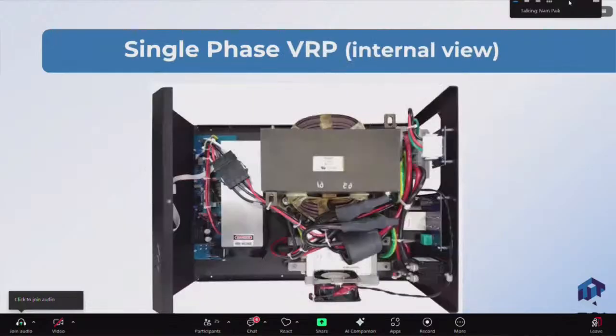Okay, this is what it looks like. When we pop open the cover, this is what you will see from the top. This is the buck-boost transformer. This is the control board with the microprocessor and the IGBT inverter system, AC to AC conversion stage, operating at 20 kilohertz to add and subtract voltage through this buck-boost transformer. On the bottom here, you will see a big EMI RFI filter to make sure that high-frequency noise is not fed back to the line.